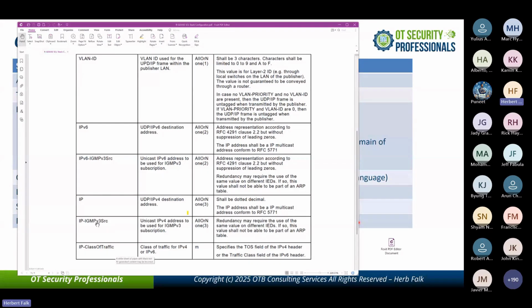But if you look at this one requirement, this allows spoofing of IP source addresses. We'll get into why that is, but R-GOOSE, in order to prevent multicast storms, uses source-specific multicasting in IGMP v3. So if you take a look at a subscriber who's subscribing IGMP v3, it needs to have a consistent IP source address for that subscription.